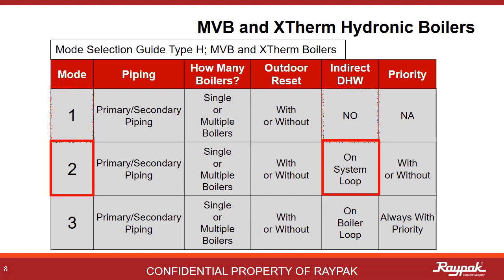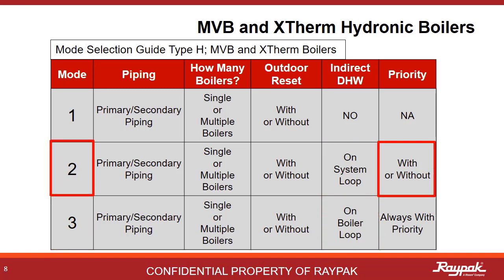If there is an indirect system present on the system loop, then it is a Mode 2. If the indirect is present on the boiler loop, then it's a Mode 3. Mode 2 can be run with or without priority, while Mode 3 is always with priority.